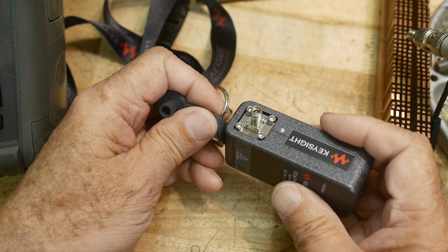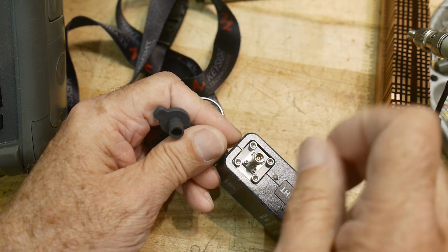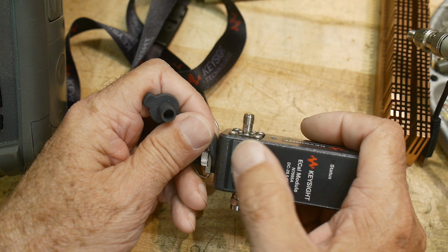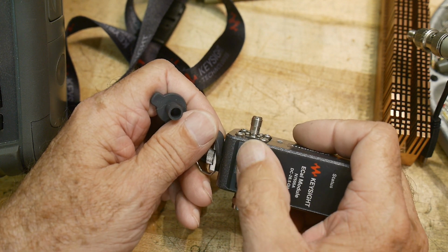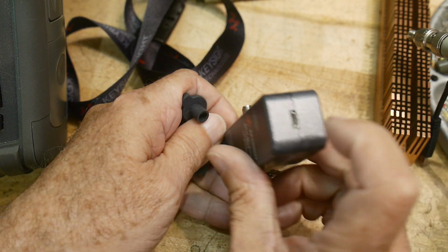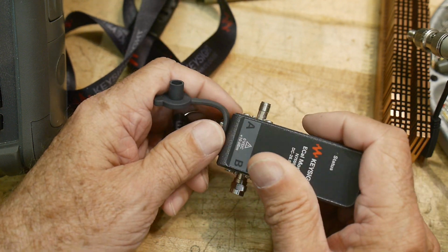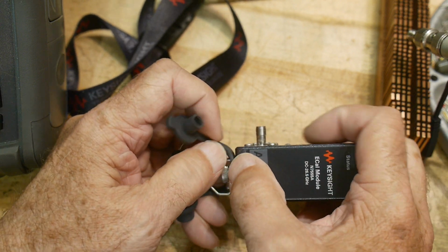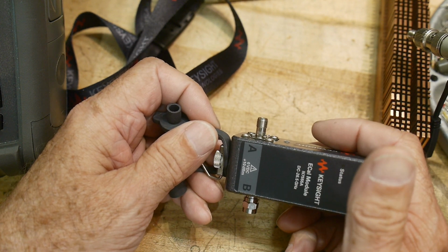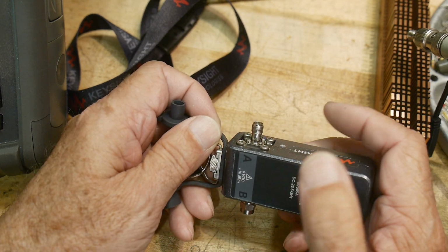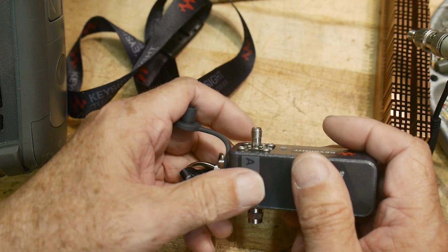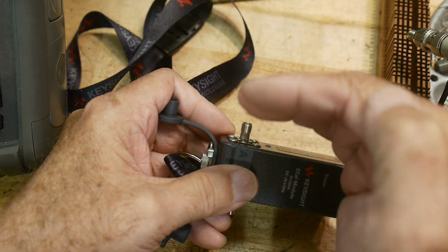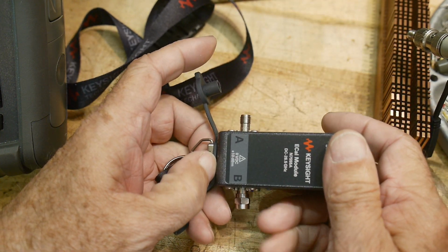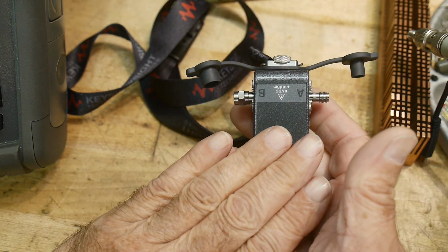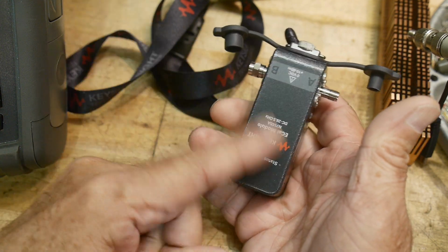And it's programmable. So instead of you unscrewing and screwing on and unscrewing and screwing on, this thing does it electronically inside. It has switching inside. So it pretends to be an open, and then it pretends to be a short, and then it pretends to be a load. And that's controlled via USB. And it can't do all those things at the exact same plane, and so it has a lot of electronic calibration data already stored in it. And so it shares that with the host instrument and says, okay, my open is at this plane, my short is maybe a few femtoseconds away from that, and here's the characteristics of my load. It has some lumpiness or something like that. Anyway, this thing is highly calibrated, and then it becomes a transfer standard to your big instrument, okay?